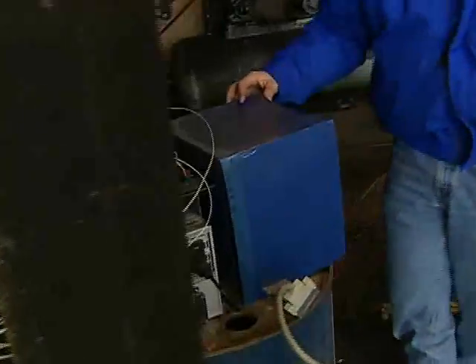we've added a couple of simulated guns. Although they don't look like guns, thermodynamically they're virtually identical. We run all of our thermocouples out into our data acquisition computer.